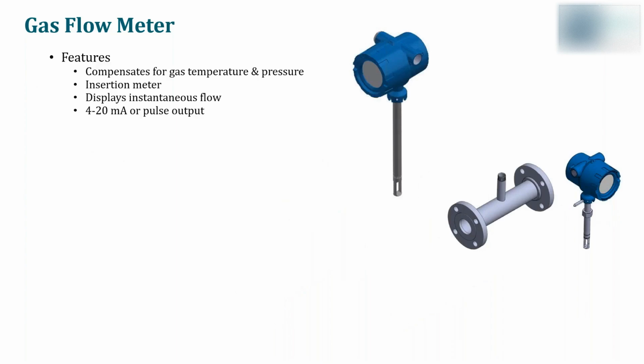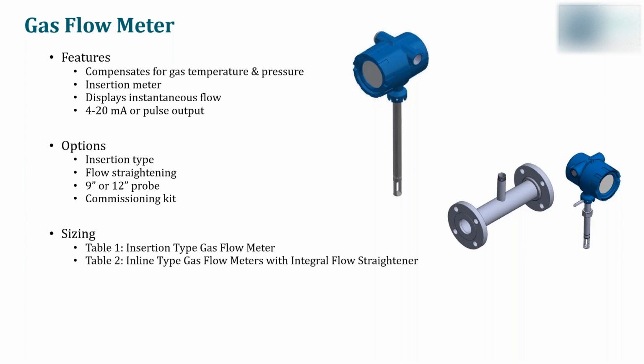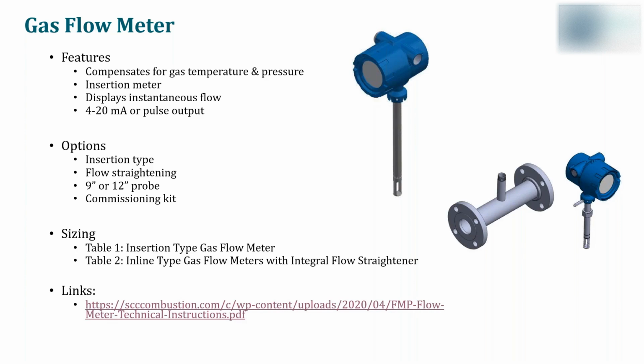Now, features include, it does compensate for gas temperature and pressure. It is an insertion meter. It provides you with instantaneous flow, and it does have 4 to 20 milliamp or pulse output. Options include, it's an insertion type meter. They do offer a flow straightening option as well. You can get it in either a 9 or 12-inch probe, and we also do offer this as part of a commissioning kit. In terms of sizing, in the links below, you could either go to table 1 or table 2, and based on the line size, select the appropriate flow meter for your application.